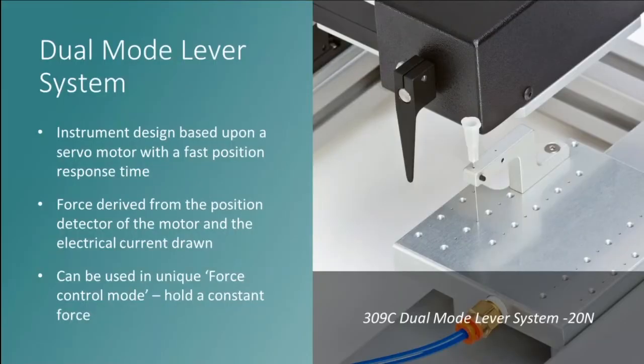So how does this so-called dual mode lever actually work? To briefly explain, the design of the instrument is based upon a servo motor, and this servo motor has a very fast step response time. The servo motor provides actuation, and thus it stretches and shortens the sample. It also has a very accurate position detector to provide feedback as to its position at any given moment.